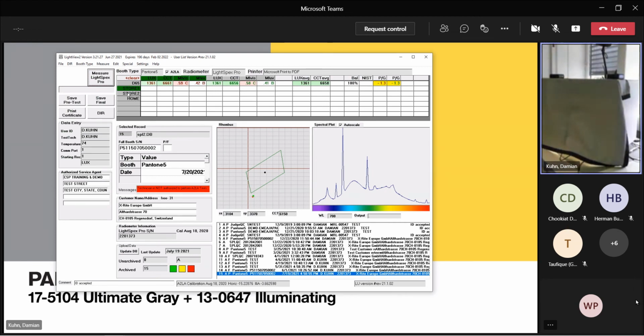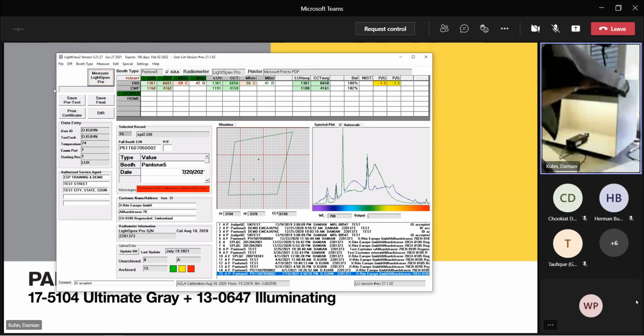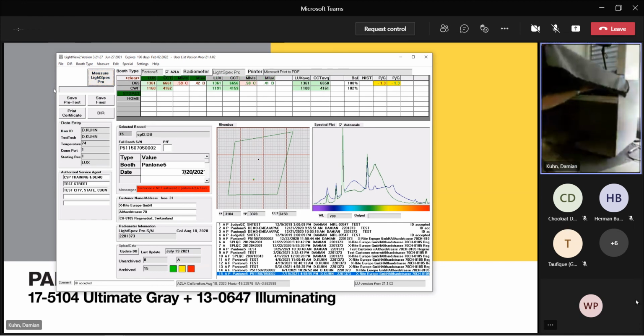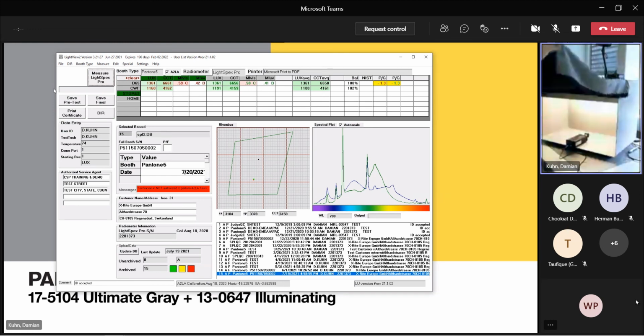So now I should wait approximately 1 or 2 minutes to give that light source some time to stabilize and warm up. Then it's as simple as clicking once to take our first reading, and a second time to take the second reading. Then we can move onwards with the next light source in the sequence.